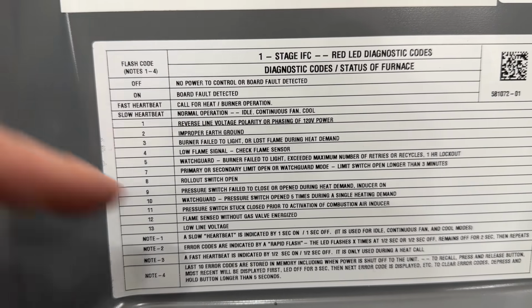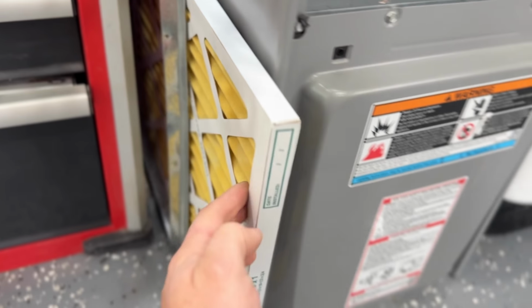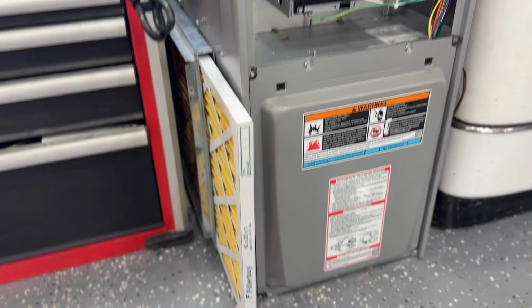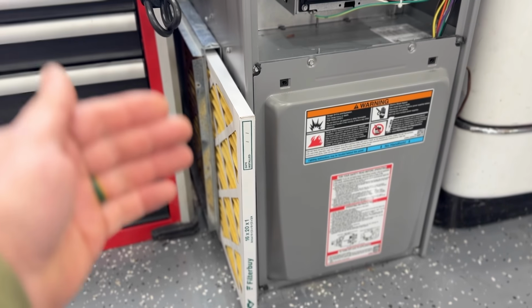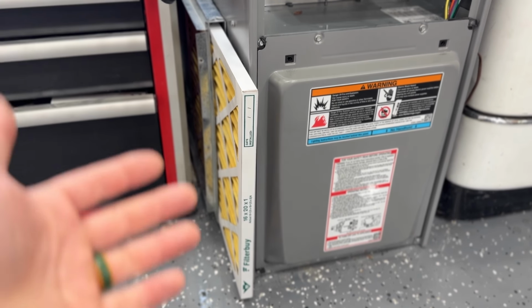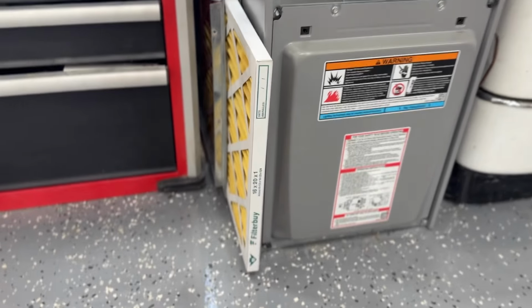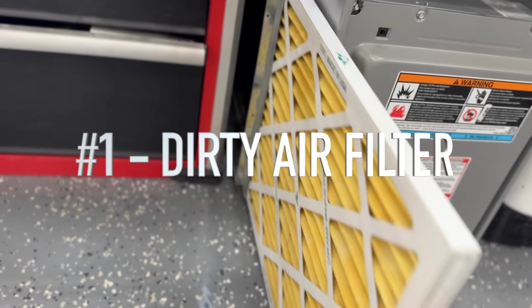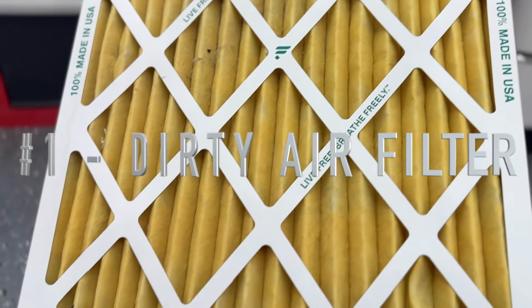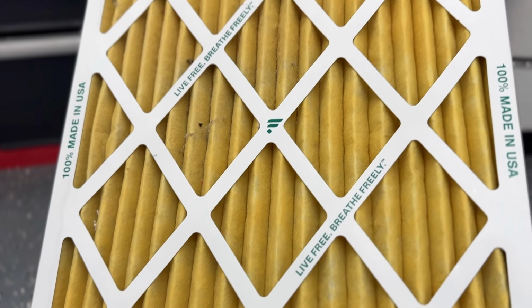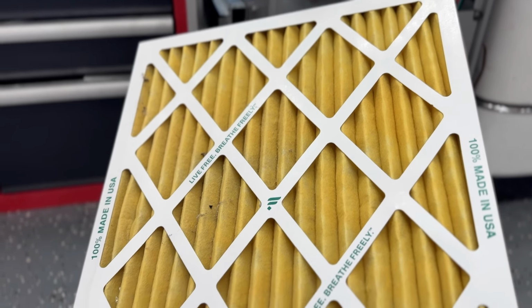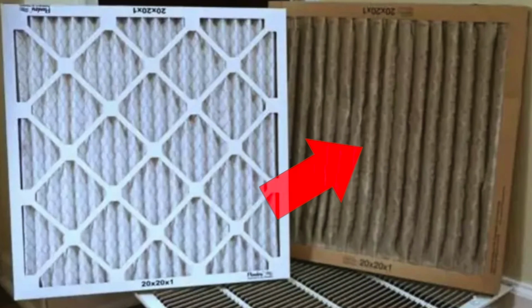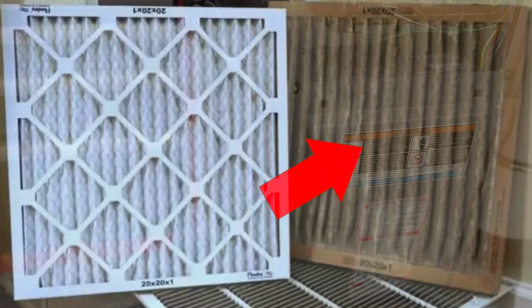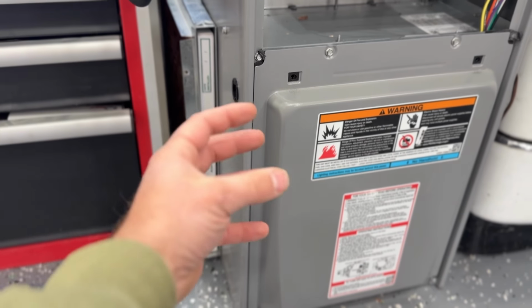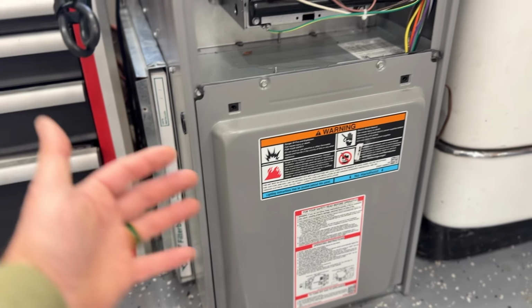All right, so number 1 is easier than you might think, and this happens so often as an HVAC contractor. We roll up to a job, they say, my gas furnace isn't working, and it ends up being a super clogged air filter. So the first thing you want to do is check your air filter and see what it looks like. If it is clogged like this, that could very well be the reason why your gas furnace is not working.